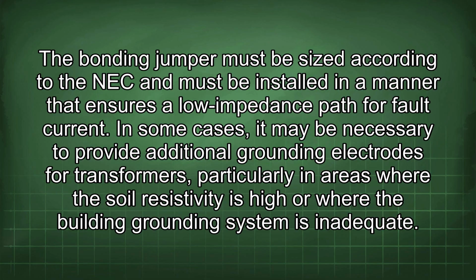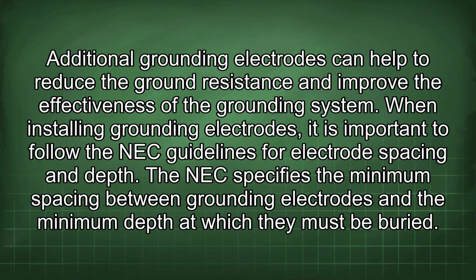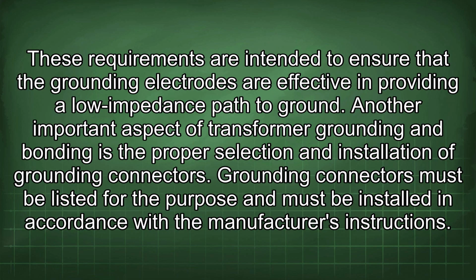In some cases, it may be necessary to provide additional grounding electrodes for transformers, particularly in areas where the soil resistivity is high or where the building grounding system is inadequate. Additional grounding electrodes can help to reduce the ground resistance and improve the effectiveness of the grounding system. When installing grounding electrodes, it is important to follow the NEC guidelines for electrode spacing and depth. The NEC specifies the minimum spacing between grounding electrodes and the minimum depth at which they must be buried. These requirements are intended to ensure that the grounding electrodes are effective in providing a low impedance path to ground.